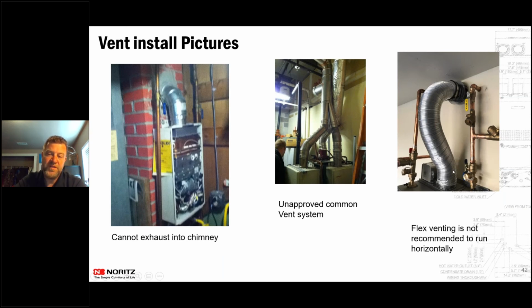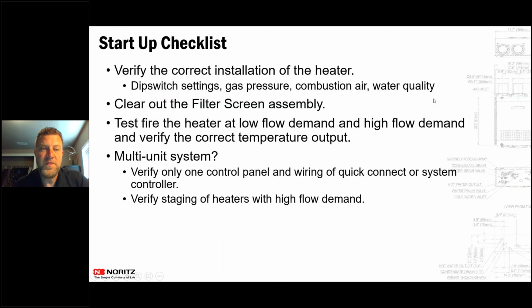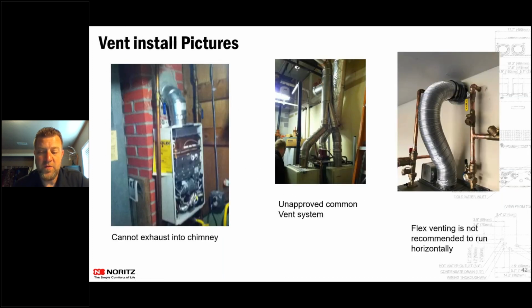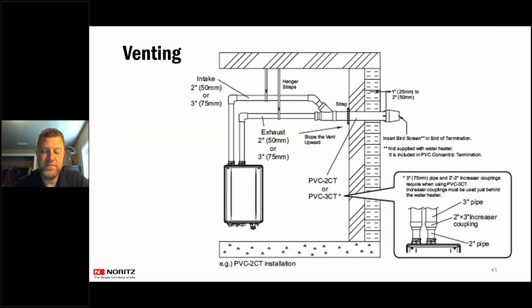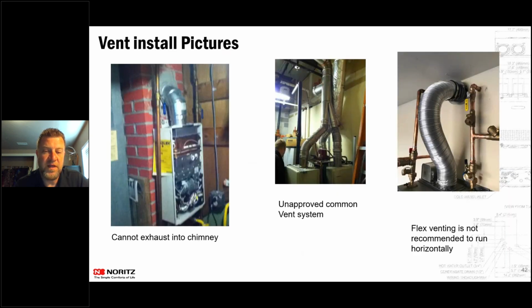So this one on the far side, we do make a unit that has a flexible polypropylene venting that's inside of this. This is just a protective cover, but they ran it out the side of the house and not up to the existing B-vent. So our flexible venting is not recommended to go horizontally. It goes vertically through the existing B-vent, not through the side of the house. Any questions on the venting and combustion?